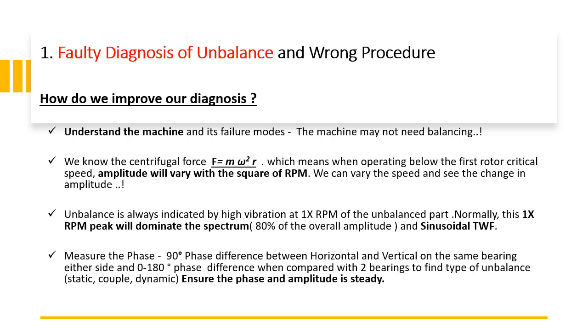Measuring phase also helps confirm unbalance. You should see a 90-degree phase difference between the horizontal and vertical directions on the same bearing, and 0 to 180-degree phase difference comparing two different bearings on either side. Based on this you can confirm the type of unbalance: approximately 0-degree phase difference indicates static unbalance, 180-degree difference indicates couple unbalance, and values between 0 and 180 indicate dynamic unbalance. Phase and amplitude must be steady. Rotor inspection also gives a fair idea of the machine condition.